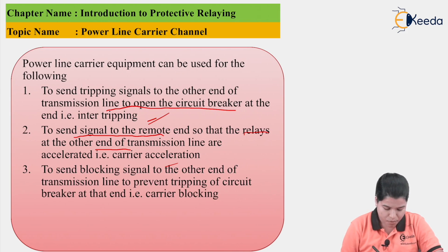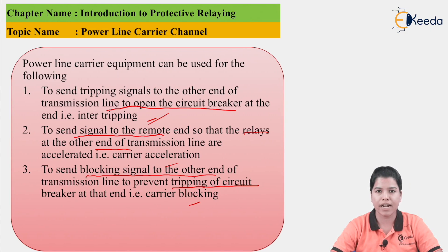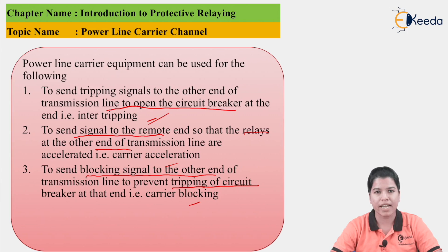Next is to send a blocking signal to the other end of the transmission line to prevent tripping of the circuit breaker at that end. This is called carrier blocking. There are two types of conditions: normal condition and abnormal condition. The protective equipment should operate only in case of abnormal condition. Hence, the power line carrier channel can be used to send the blocking signal to the circuit breaker so it might not operate under normal condition. Also, there are two types of protection — primary protection and backup protection. If the circuit breaker is used as backup protection, then it must not operate for the primary protection. The blocking signal can be sent by using the power line carrier channel.